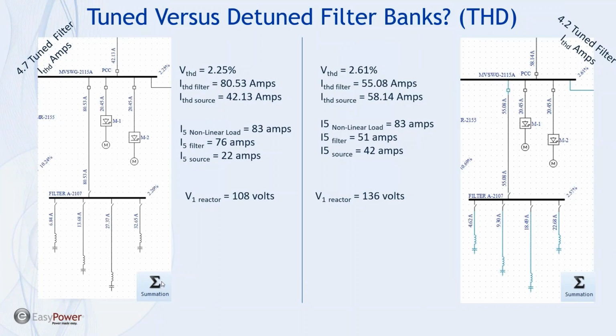I've done a summation here, and I've plotted the currents. You can see that for the harmonic current injection in our plant, we have 42.13 amps flowing out towards the source. For the detuned part of the project, we have 58 amps here. So I've changed the filters to detuned, 4.2 tuning versus 4.7 tuning. You can see that a value of 42 amps flows towards the point of common coupling versus 58. And if you look at the filter branches, this four-stage filter bank is in service. You can see we have 80.53 amps versus 55.08 amps.